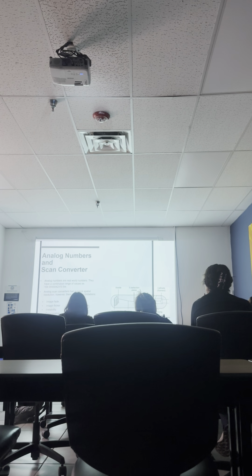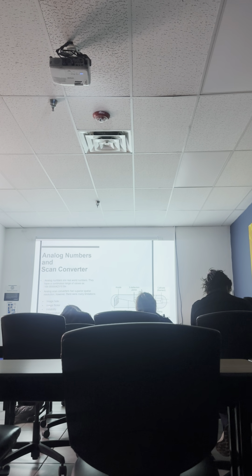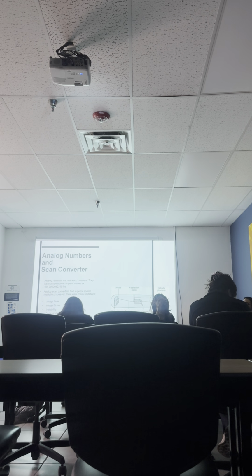Okay, but there were limitations. We have image fade, image flicker, instability, and deterioration. Are those conducive to diagnostic images? No, they're not. We may have superior spatial resolution, but everything else would deteriorate. And it used these types of converters.